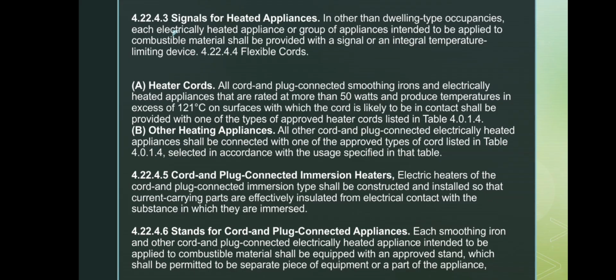For immersion heaters, these must be built and installed so that all current carrying parts are fully insulated from the liquid they are placed in. Finally, for stands, every smoothing iron and other heated appliance meant to be used on combustible material must have an approved stand, either attached or as a separate accessory.